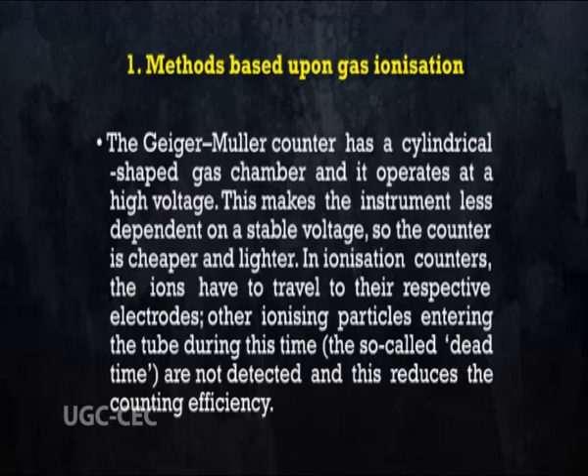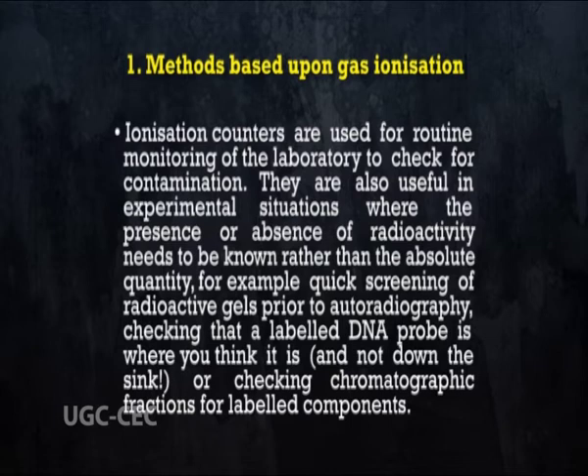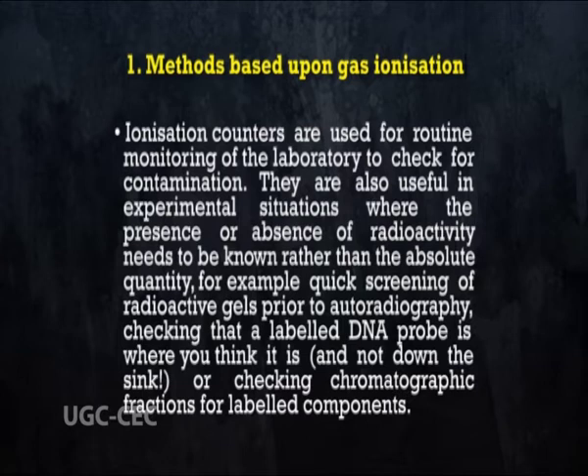In ionization counters, the ions have to travel to their respective electrodes. Other ionizing particles entering the tube during the so-called dead time are not detected, and this reduces the counting efficiency. Ionization counters are used for routine monitoring of the laboratory to check for contamination. They are also useful in experimental situations where the presence or absence of radioactivity needs to be known rather than the absolute quantity — for example, quick screening of radioactive gels prior to autoradiography, checking that a labeled DNA probe is where you think it is, or checking chromatographic fractions for labeled components.